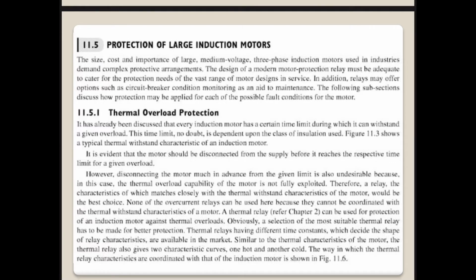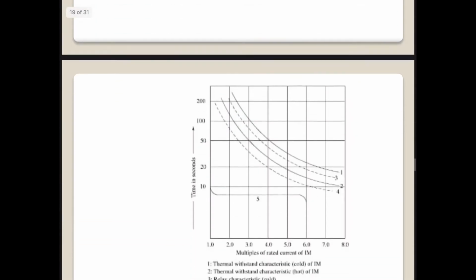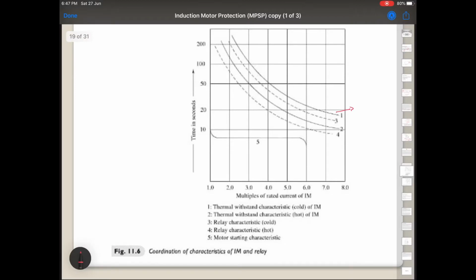Similar to the thermal characteristics of a motor, the thermal relay also gives two characteristic curves, a hot curve and a cold curve, which we have already discussed. That is shown in figure 11.6. Here you can see the characteristics of a motor in cold condition, the characteristics of a motor in hot condition, and lines 3 and 4 are the thermal relay characteristics during cold condition and hot condition. This exact curve matching can be pre-ordered from the manufacturer, or relays are also available in the market with settings given on them.